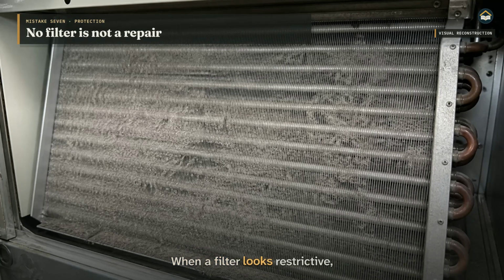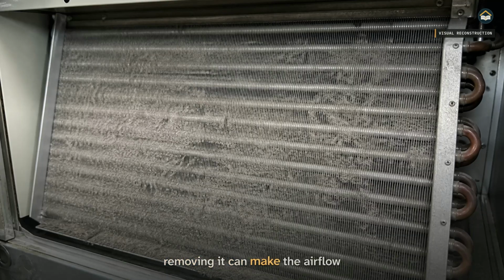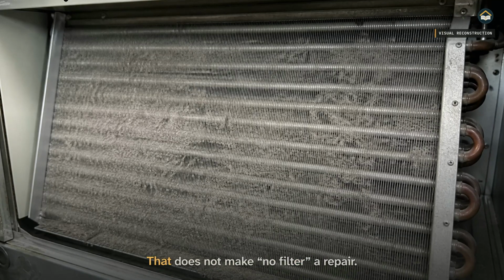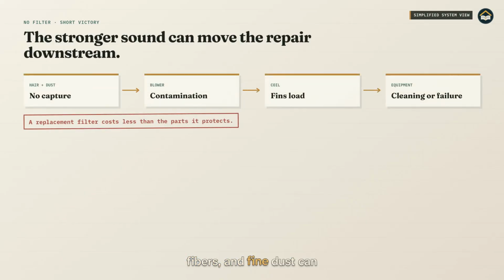When a filter looks restrictive, removing it can make the airflow sound stronger. That does not make no filter a repair. Without the filter, hair, fibers, and fine dust can collect on the blower and evaporator coil. ASHRAE warns that the short-lived airflow victory can end with a contaminated coil and equipment failure. A replacement filter costs far less than cleaning or replacing what it was meant to protect.